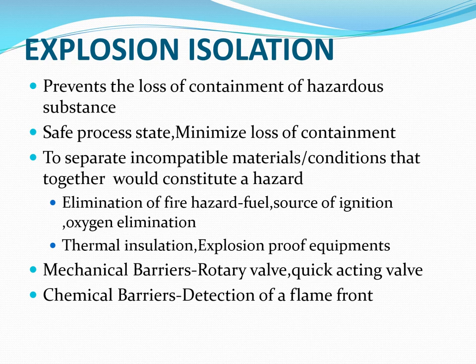A process without interconnections is rare, and any process with interconnections is subject to flame propagation through ducts. Measures are needed to prevent an explosion initiated in one plant from propagating through pipes, ducts, chutes, and conveyors to other parts. Barriers should be created to avoid explosion propagation. There are two basic types of isolation barriers: mechanical barriers, such as rotary valves and quick-acting valves, and chemical barriers, which use detection of the flame front to trigger suppression.